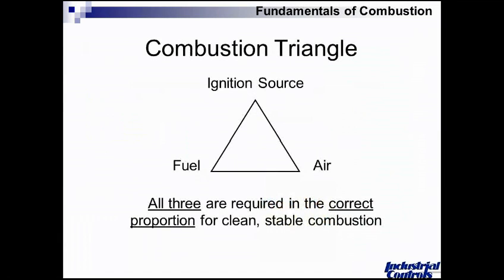Going back to the basics, we're going to explore combustion. That involves the discussion of the combustion triangle. To have a complete triangle, we need three sides. At the upper apex, we have some sort of an ignition source — something that triggers our reaction, something that's hot. Lower left, we have some type of fuel, carbon-based: it could be paper, rubbish, natural gas, oil, coal — anything with free carbon. On the right-hand side, we have air, either the air we breathe, pure oxygen, or some combination thereof. All three are required in the right proportions for clean, stable combustion.